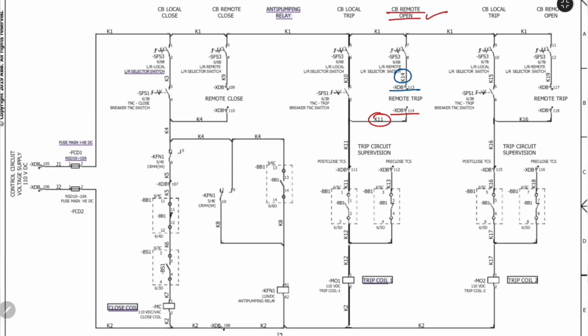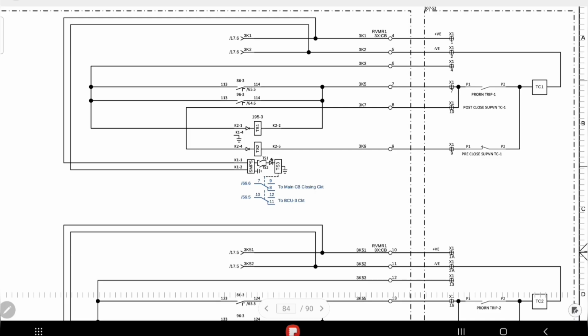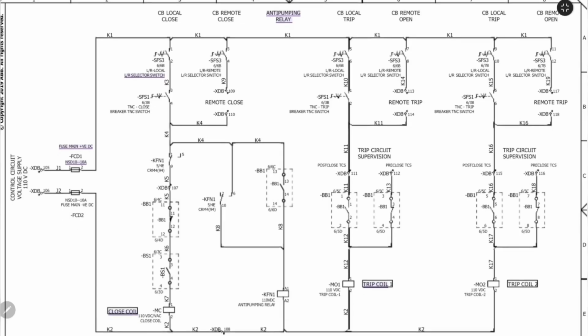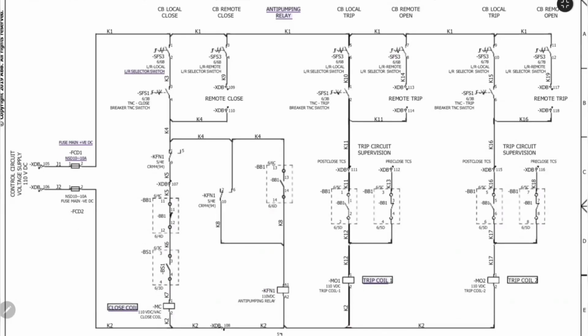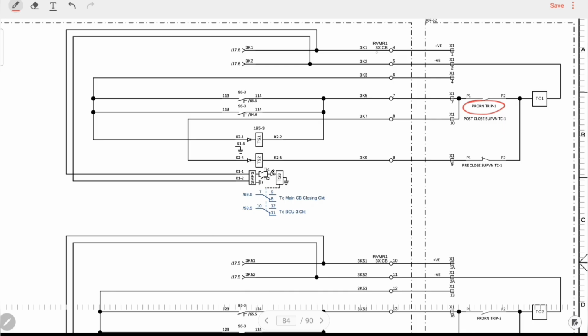Now let's wire the most important circuit in the entire control scheme, the protection trip circuit. Unlike manual operations, protection tripping must never depend on the local remote selector switch. Whenever an overcurrent, earth fault, differential, or any other protection operates, the breaker must trip immediately, regardless of the operating mode. Inside the Siemens panel, terminals 3xCB4 and 3xCB5 provide the internal DC control supply. Install a shorting link between terminals 3xCB4 and 3xCB6.